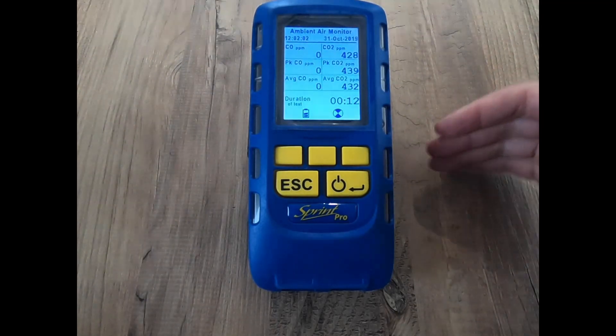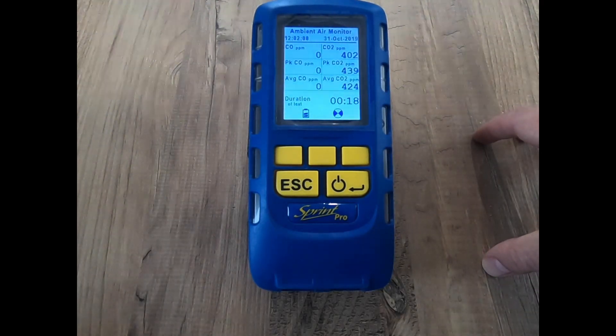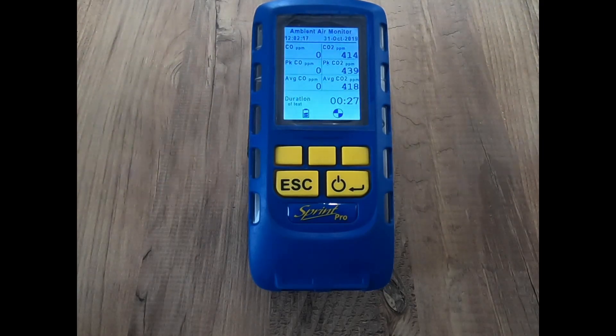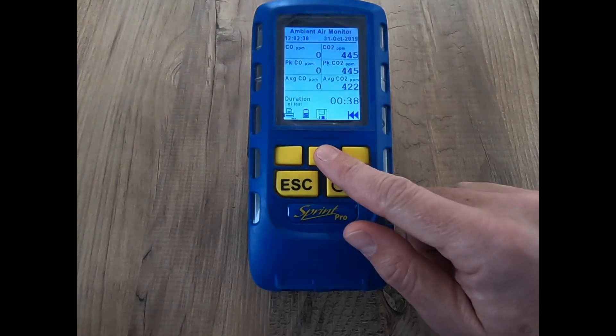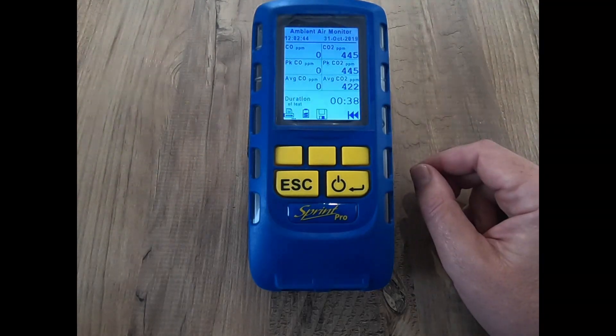As a 15-minute test, it will log a recording every minute. In typical Blue Peter fashion, I did a 30-minute test earlier today with a couple of little peaks of CO2 — just me breathing on it — but it's enough to show you what this test will look like when it's completed. You can let it run to completion, or if you want to finish it early you can press escape and quit. When you're at that stage, whether it's finished properly or ended early, you can save it into the logs.